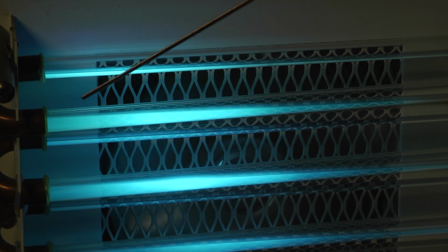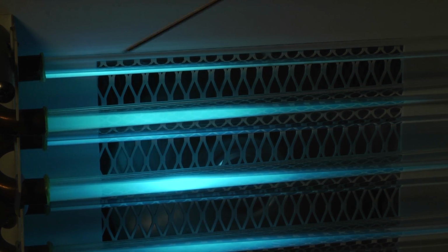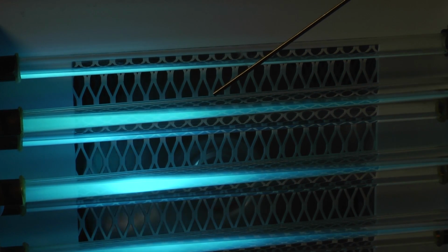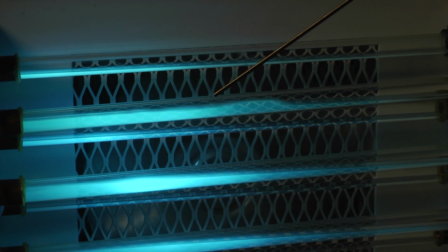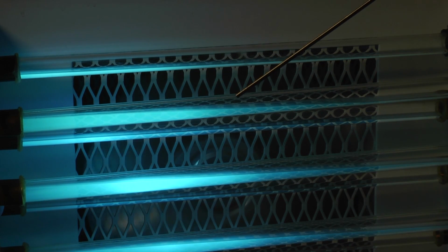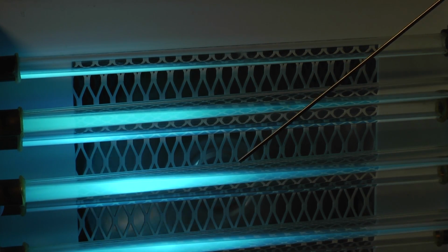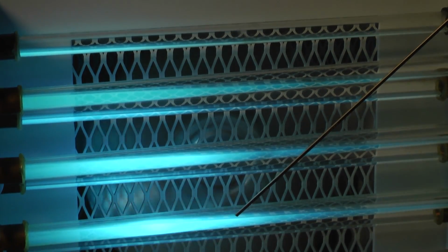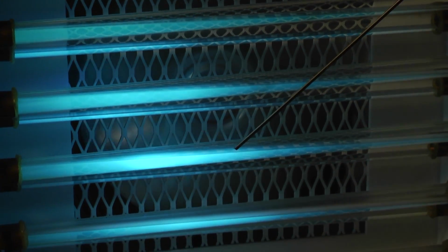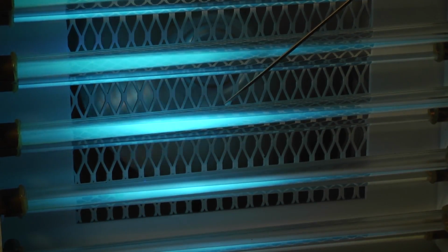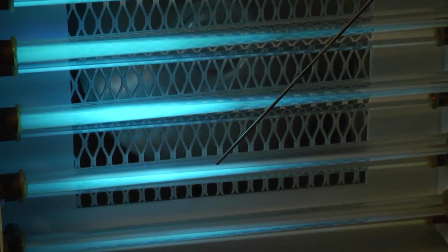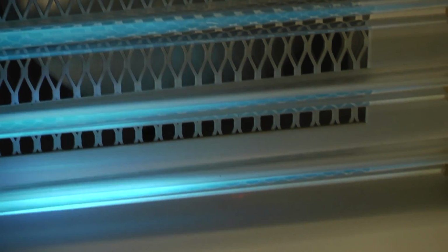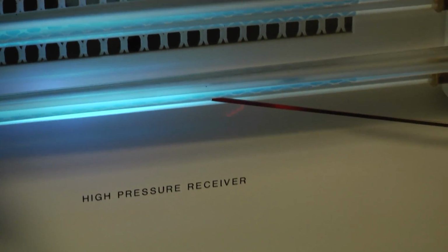Now, as the refrigerant travels through additional places in the condensing coil, you can see that it's starting to change state. And what we're starting to see is larger amounts of liquid condensing and less vapor present. As we travel through other tubes, we're going to continue this condensing, or saturation process, where we're rejecting heat and condensing the refrigerant back to a liquid. We're going to continue to move through, and you can see the ratio change more and more. Finally, we're going to get down to the last tube in the condenser coil.